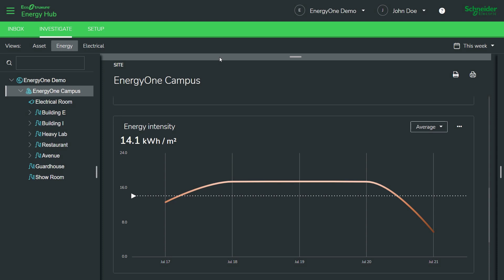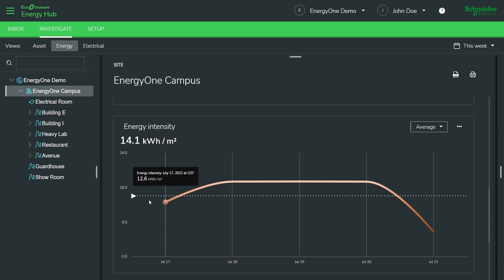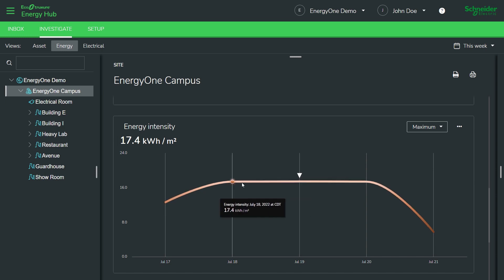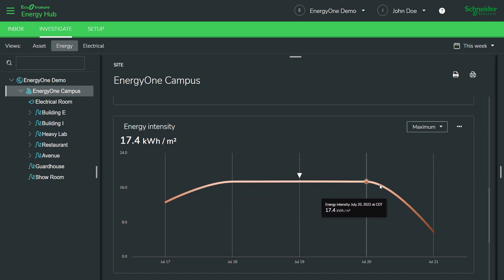Often, in building campuses, an interesting number to look at is the energy intensity. Meaning, what is your energy consumption per square foot or square meter of area? So, in our example here, you can see the average is about 14 kilowatt hours a square meter. We can also look at the maximum which appears to be 17 and it looks like between July 18th and July 20th, we hit that maximum energy intensity.